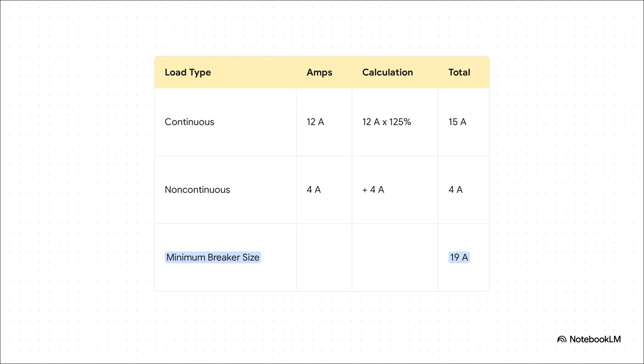Let's walk through a quick example. So imagine a circuit with, say, 12 amps of continuous lighting and a 4-amp non-continuous load, like a fan you turn on and off. Now, simple addition would give you 16 amps, but that's not safe. Instead, we have to apply the rule. We take the 12 continuous amps and multiply by 125%, which gives us 15. Then we add the 4 non-continuous amps. The result? 19 amps. This means we actually need a 20-amp breaker, not a 15-amp one. That 5-amp difference is your entire safety margin against heat buildup.